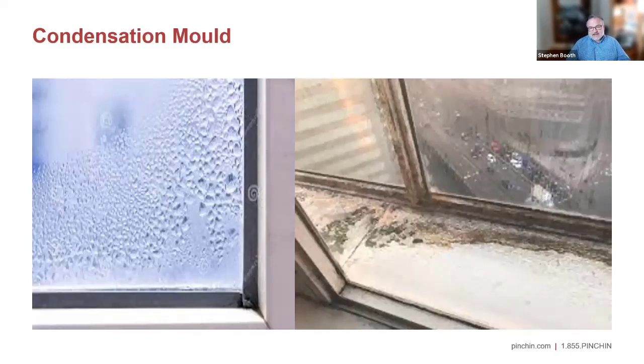The problem is that in Canadian buildings in winter, if you're keeping a building at 40% relative humidity, you are almost definitely likely to end up with condensation on the windows, and you have a very good chance of condensation inside wall cavities and other locations you can't see, which could lead to mold growth. So we have to be very cautious when we look at humidification in Canadian buildings during winter months.